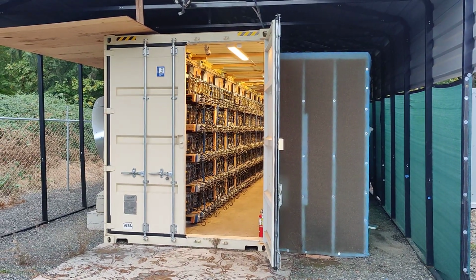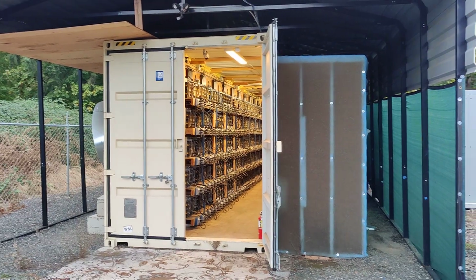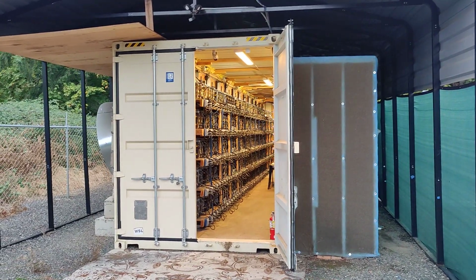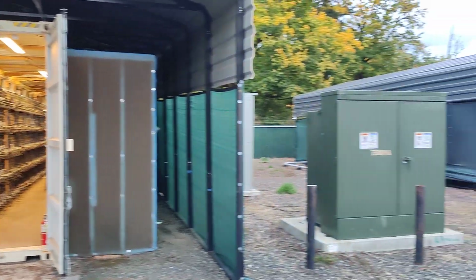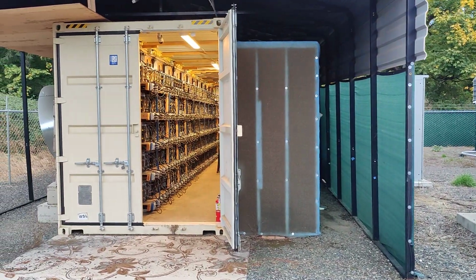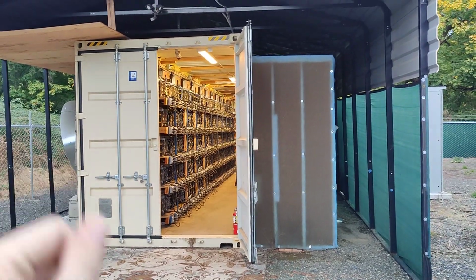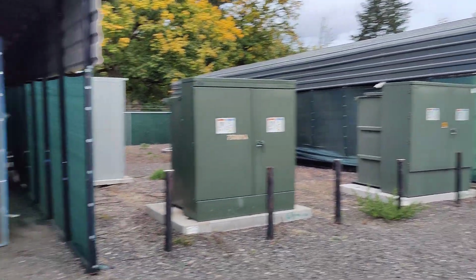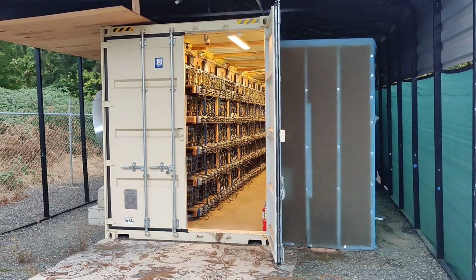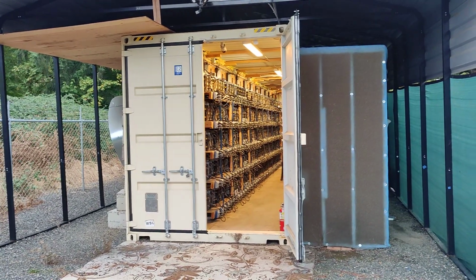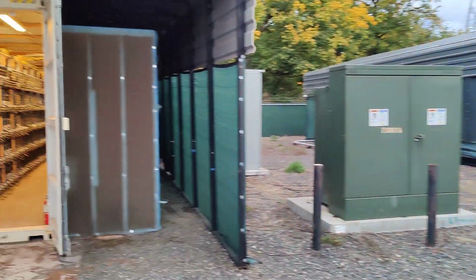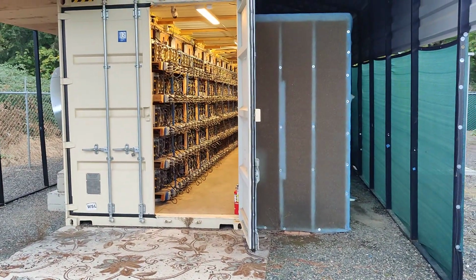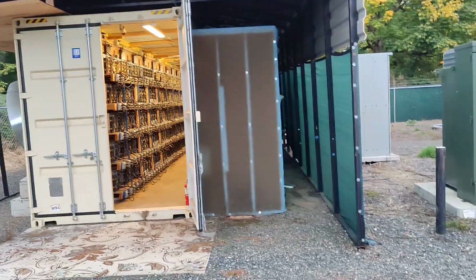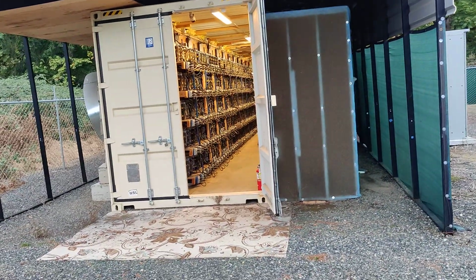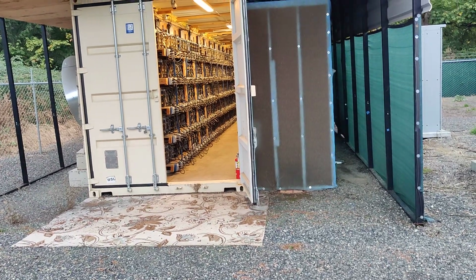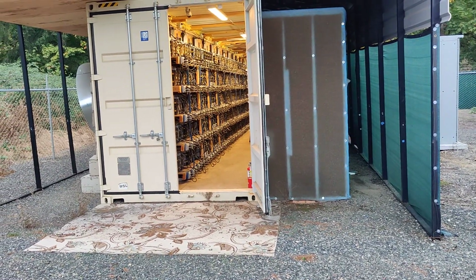Today's video we're going to be talking about our humidity sensors that we have set up to monitor how high the humidity gets at night. This is for our 750 kVA mining facility here, Mining Connex, actually we have two of them. The other one's a 1 megawatt transformer, and we run S17 Plus, S19 Pros here. They're both fully loaded, so we're using all the watts. So the situation we have is it's October, it's getting cold, temperature is dropping to 35, even 30 at night. We're getting very close to zero, and then we're gonna have ice and snow and all that.